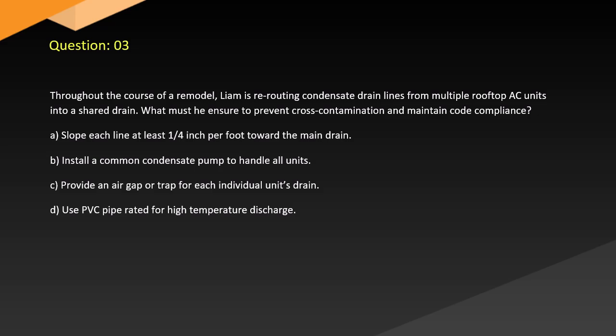A. Slope each line at least 1/4 inch per foot toward the main drain. B. Install a common condensate pump to handle all units. C. Provide an air gap or trap for each individual unit's drain. D. Use PVC pipe rated for high temperature discharge.